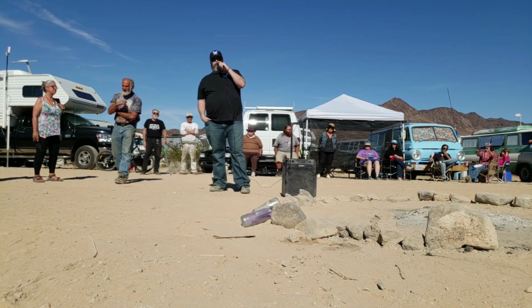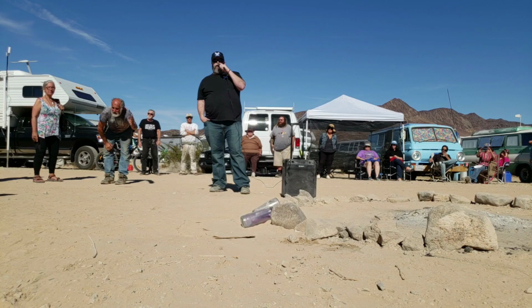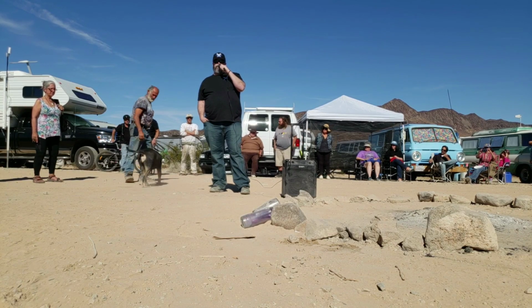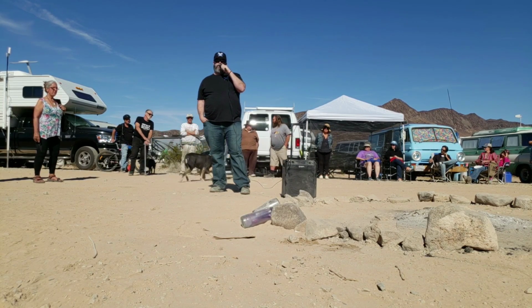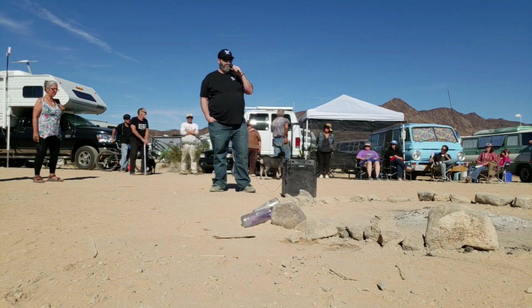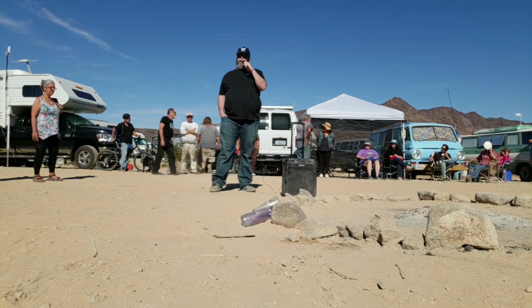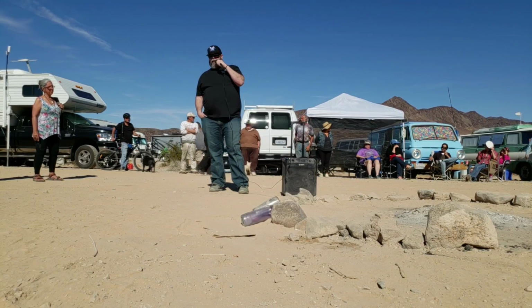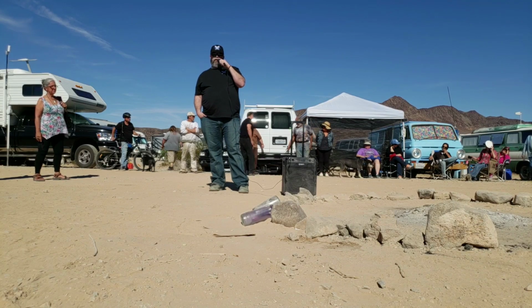So that's right, 42 usable amp hours on a brand new set of 6-volt batteries before you started to damage them, out of 225. They say you can use 50% of the battery, 50% of the power, but the part they leave out is that 50% is variable based on the load.